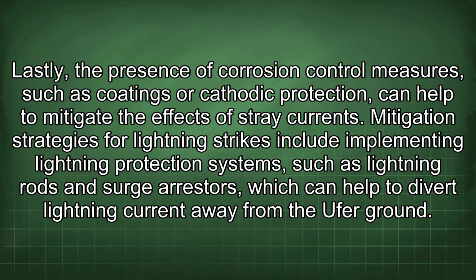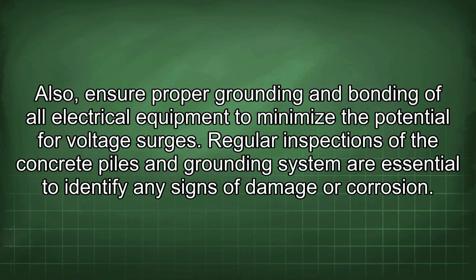Mitigation strategies for lightning strikes include implementing lightning protection systems, such as lightning rods and surge arresters, which can help to divert lightning current away from the Ufer ground. Also, ensure proper grounding and bonding of all electrical equipment to minimize the potential for voltage surges. Regular inspections of the concrete piles and grounding system are essential to identify any signs of damage or corrosion.